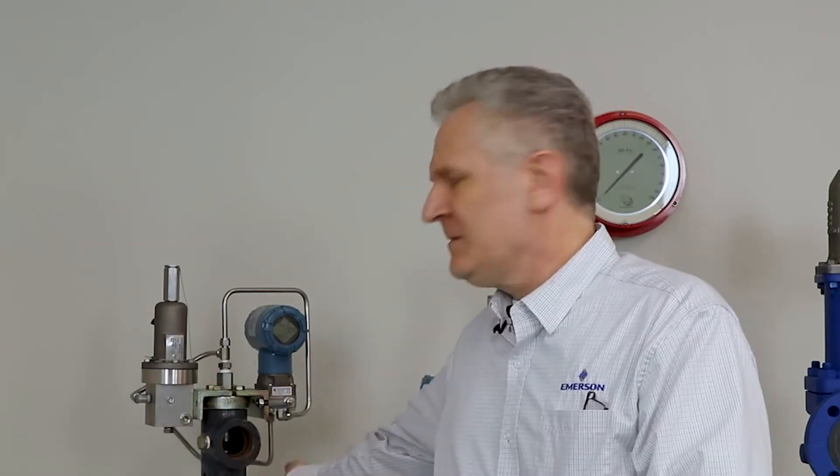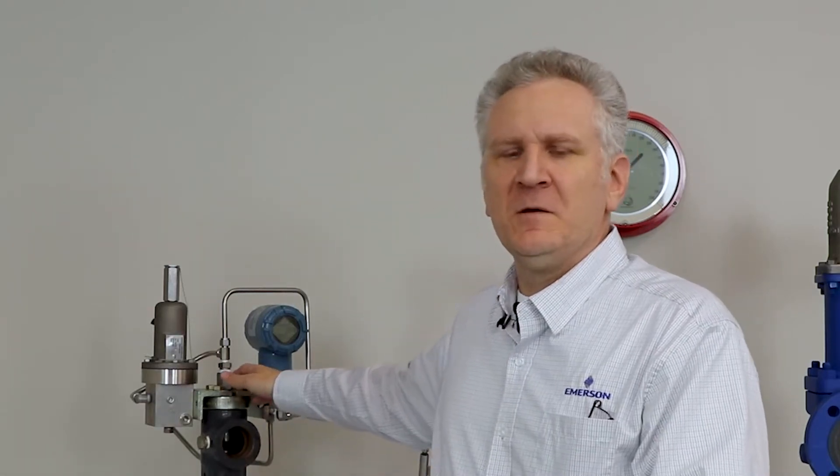The Rosemount Differential Pressure Transmitter monitors the differential pressure between the valve inlet and the main valve dome. Below set pressure or opening pressure of the valve, dome pressure will equal the inlet pressure and no pressure will be measured by the transmitter.